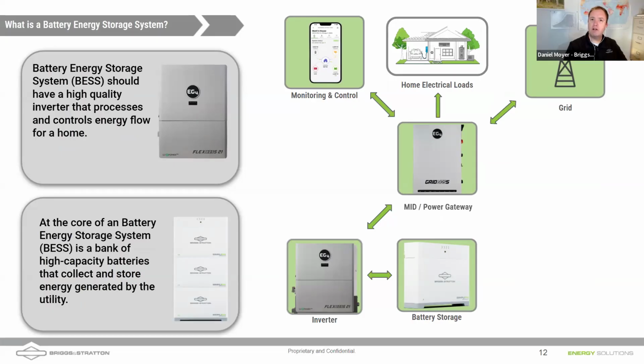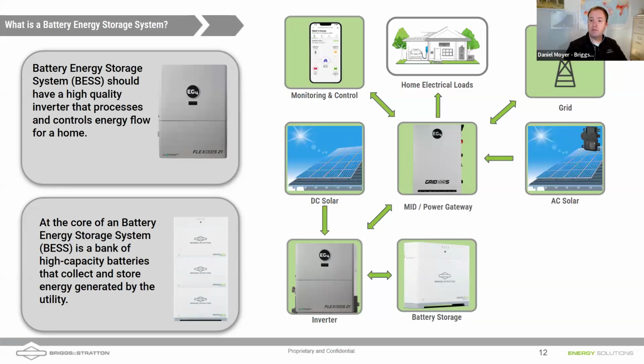Now we're going to jump into a little bit more single line diagrams here in a second, but we got something very similar here where we're set up. Grid coming into the gateway, then flowing to the inverter and the battery, right? The grid can then send AC down to that inverter. We can act like a battery charger, turning AC to DC, or it can turn that DC to AC, an inverter, and send it up to that GridBoss, going to power the home's loads. We can bring in DC coupled solar like before. We can bring in AC coupled solar into that GridBoss. And at the same time, we can bring in a generator as well. The idea is that we also have smart load outputs. That GridBoss is giving us the flexibility to add all of these sources without having the need to choose between one or the other. There's another great advantage, the flexibility of install, which I'll get into in a little bit later. Any questions, please pop them into the Q&A. Let me know if you've done one of these systems or why you might like EG4.